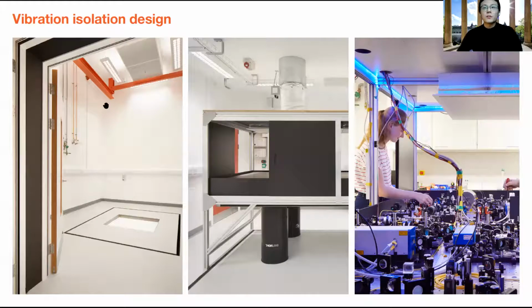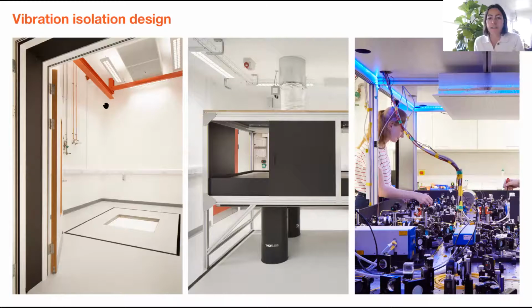The next question is: once those air springs below the keel slabs, specified for the current research requirement, are installed, will they be changeable to adapt to potential changes in research requirements in the future? Yes, absolutely. That was the primary reason for providing a full additional basement level below the labs to contain those keel slabs and air springs. In theory you could have just dug local holes below each lab to hold the keel slab, but having a full floor means they're fully accessible, and the elevator goes down to that level, allowing easy installation, replacement and maintenance of those air springs in future.